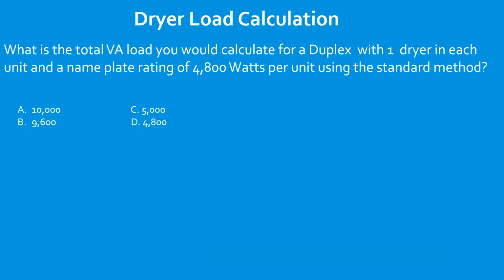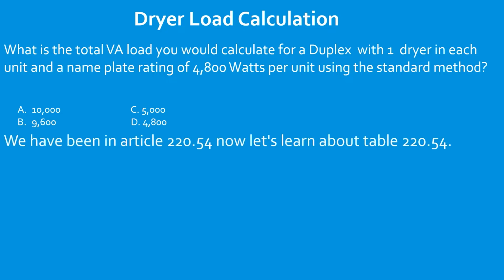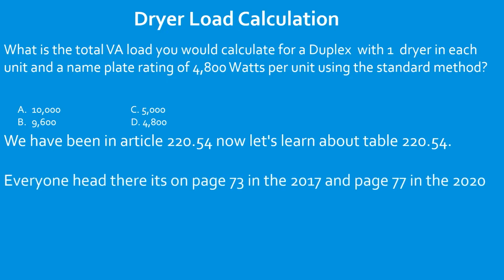What is the total VA load you would calculate for a duplex with one dryer in each unit and a nameplate rating of 4,800 watts per unit using the standard method? So up until this point, we've been in Article 220.54, but now let's learn about Table 220.54. We're on page 73 in the 2017 and page 77 in the 2020.